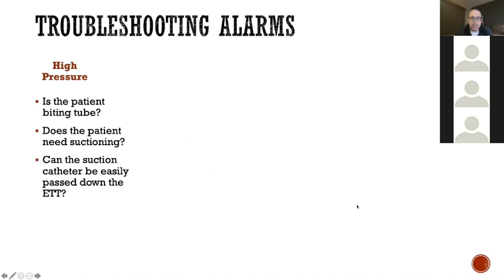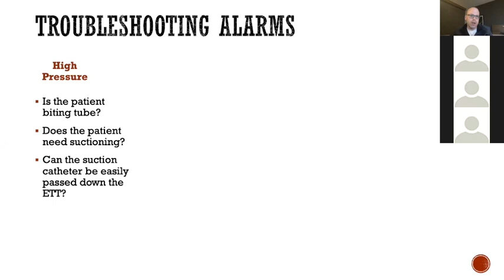So how do we troubleshoot them? For high pressure alarms, we want to look at: is the patient biting their tube, or do they need suctioning? A good test for that is, can you pass the suction catheter down the endotracheal tube? If we can, then that tube is not obstructed, right? And then we can suction them on the way out and see if that helps clear the problem. One of the common high pressure alarms is when I'm leaning against the bed and crushing the ventilator tubing against the rail. Been there, done that, you'll get a high pressure alarm. Same if you put your foot on the tubing in the back of an ambulance, you're going to get high pressure alarms. So just look for a kink in your circuit.